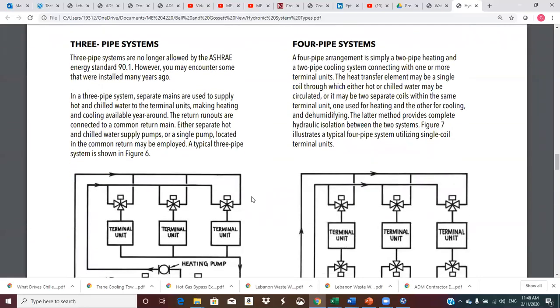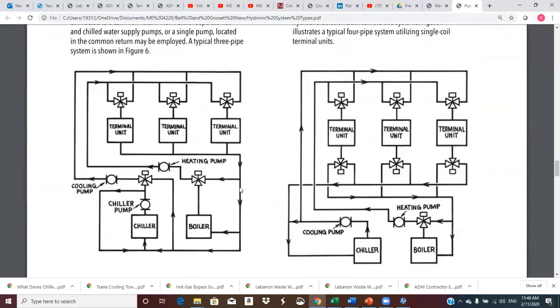Okay, what do we have here? Three pipe systems. You don't see this anymore. This is where you could have a heating pump and a chiller pump. The heating pump takes hot water and circulates it up to the terminal unit. The chiller would run the chill water pump, and then this valve would decide which one it was going to select, and then it would return all of the water. It would mix it and return it together.